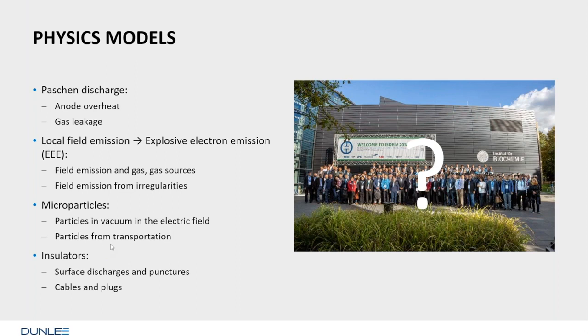I recall when in the early days still stationary anodes were used for CT, for this very old Hounsfield systems. These tubes were stationary anode tubes, but once you kicked them by throwing them into a box or something and switching on the high voltage, they started arcing again. And that was due to obviously particles inside the tube.